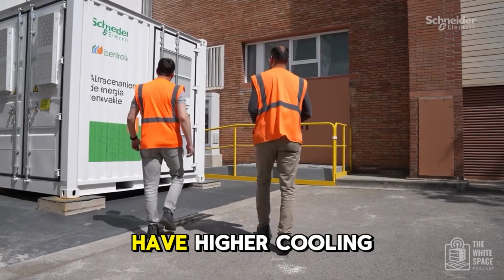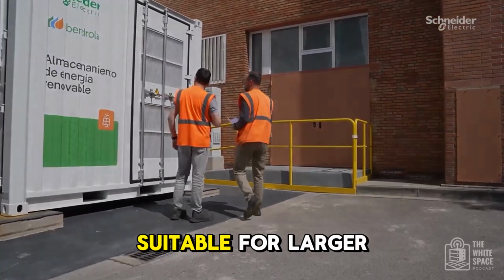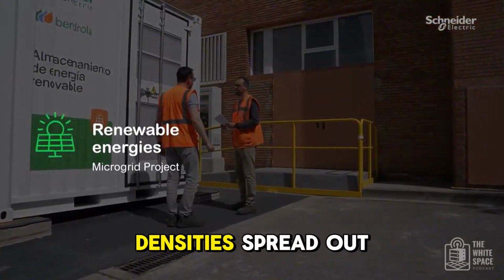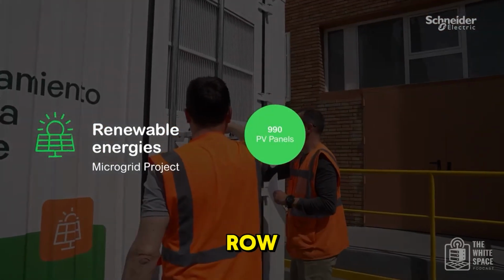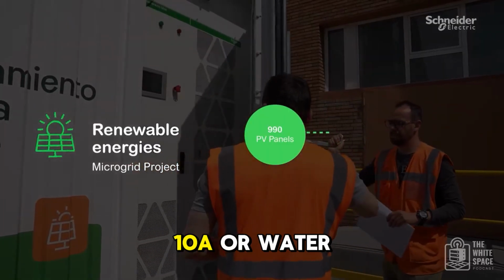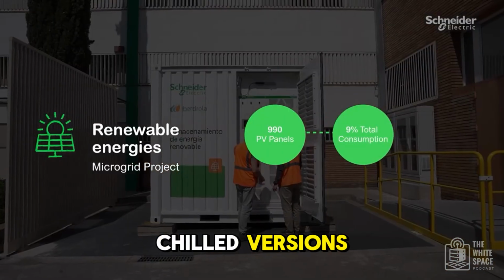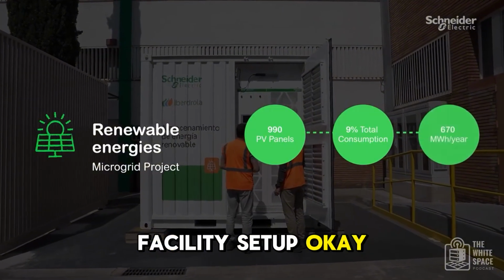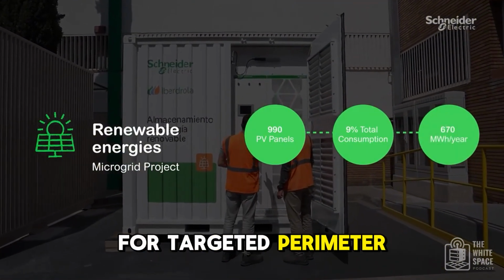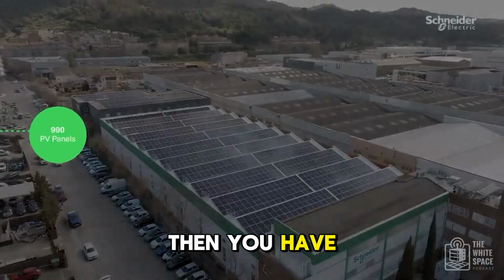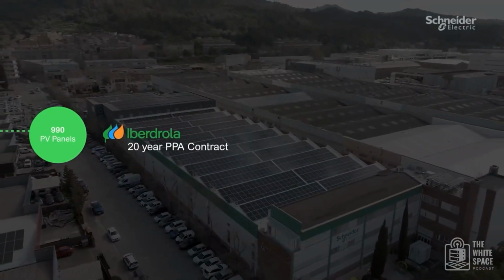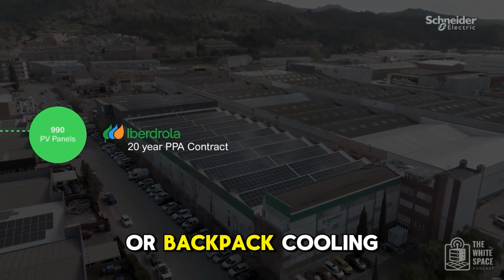These systems typically have higher cooling capacities, suitable for larger spaces even with high densities spread out. And like in-row, they come in DX using R410A or water-chilled versions, depending on the facility's setup. So, in-row for targeted, perimeter for room level cooling. What else?